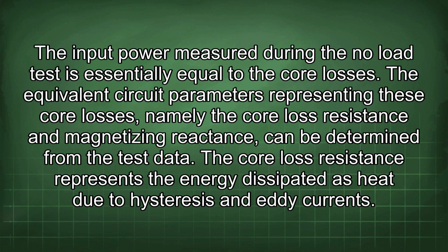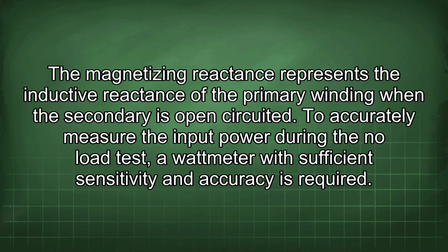The equivalent circuit parameters representing these core losses, namely the core loss resistance and magnetizing reactance, can be determined from the test data. The core loss resistance represents the energy dissipated as heat due to hysteresis and eddy currents. The magnetizing reactance represents the inductive reactance of the primary winding when the secondary is open-circuited.